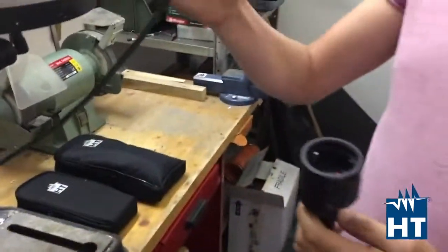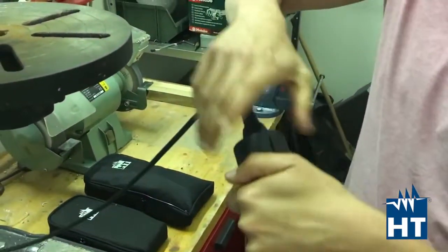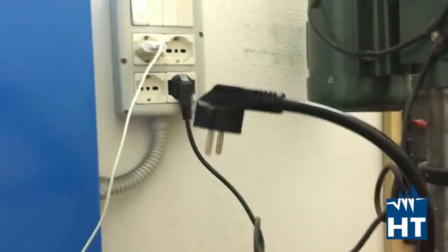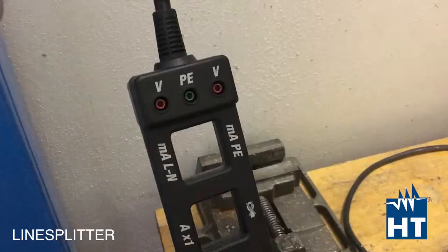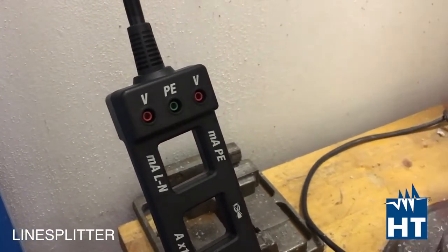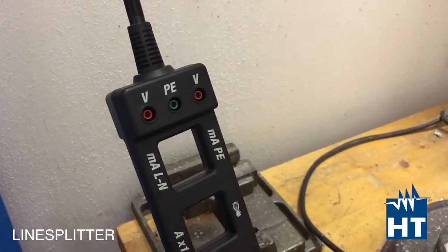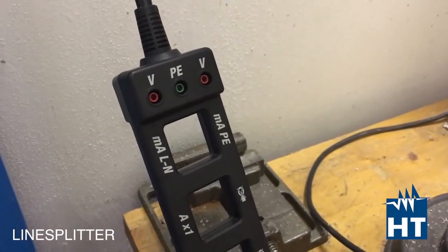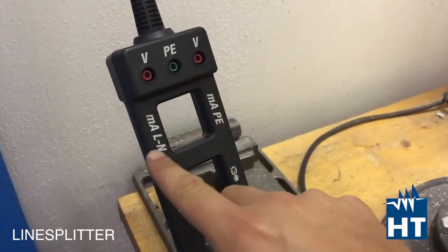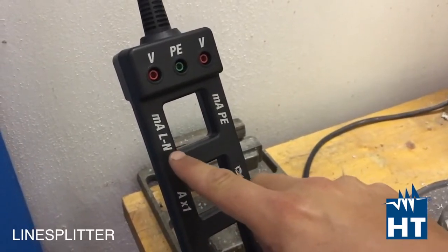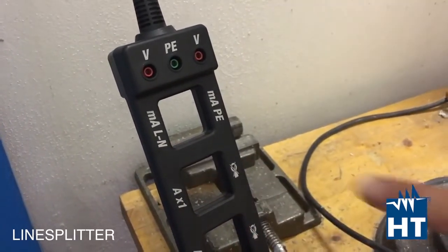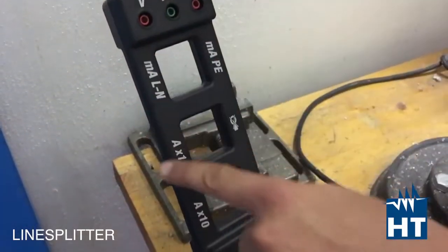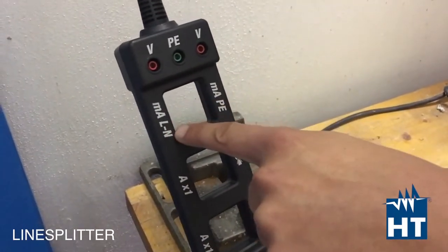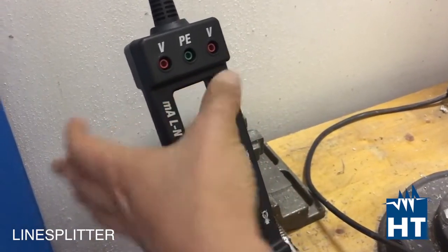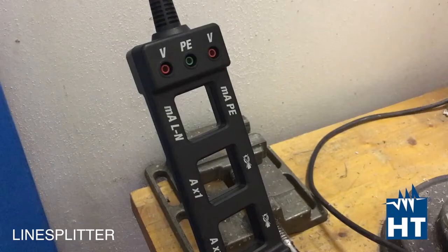So what we're going to do is take the socket of the motor and plug it inside the Linesplitter, and from the other side we're going to power the motor. Linesplitter simply divides the line: the phase conductor, the neutral conductor, and the earth or PE conductor. So you can see you have the milliamp between phase and neutral. That means you have both wires, neutral and phase, passing through this loop. So if you clamp here, you can measure the leakage between phase and neutral.